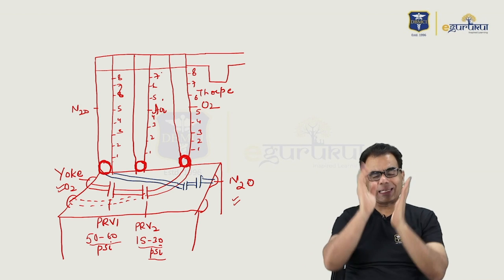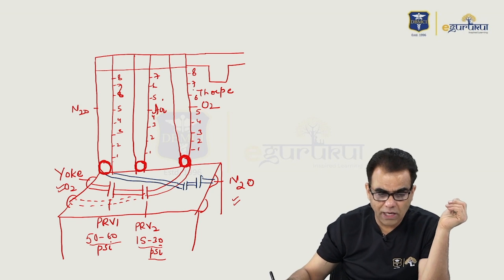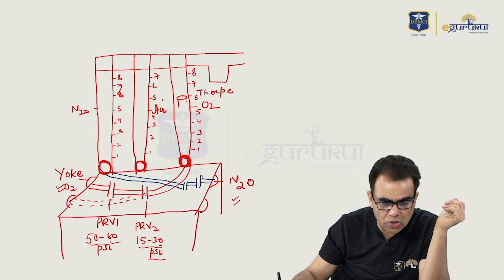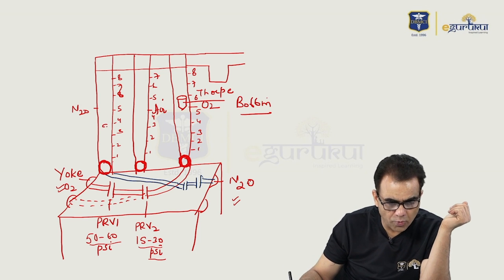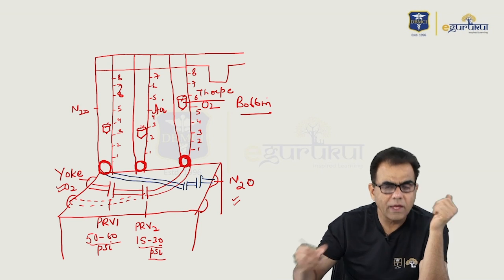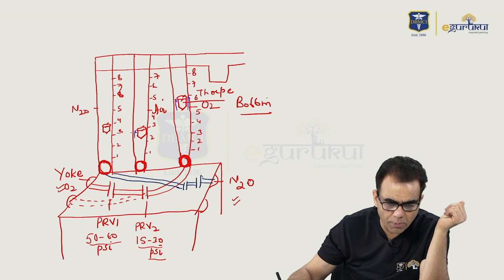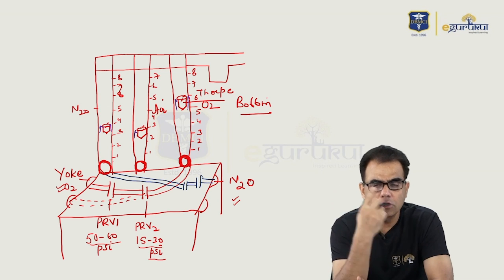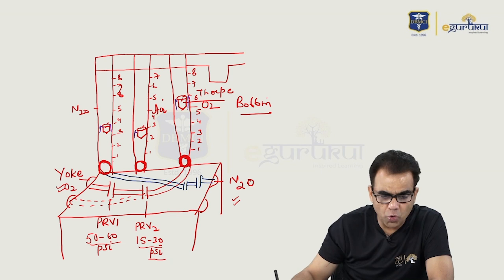These are glass tubes, but still you cannot see the gas flowing through them, so you have to be sure gases are in continuous flow. For that, they have placed an aluminium structure into each tube called a bobbin. There will be a bobbin for oxygen, for nitrous oxide, and for air. In its upper rounded part, there are cuts. When gas passes all around this bobbin, due to these cuts, it makes the bobbin rotate. If the bobbin is continuously rotating, that means gas flow is continuous.